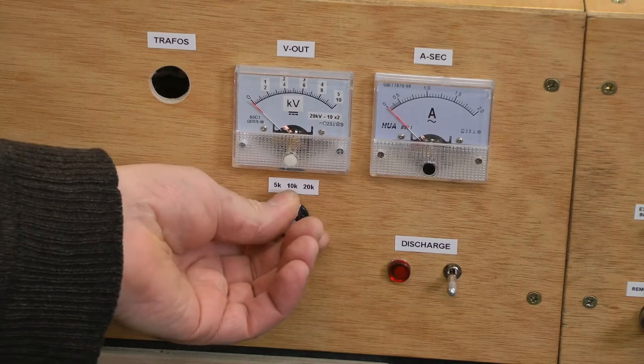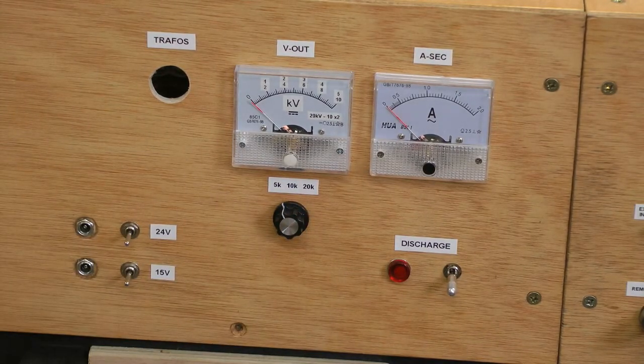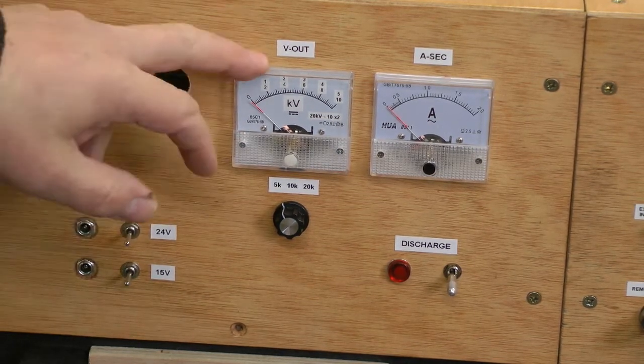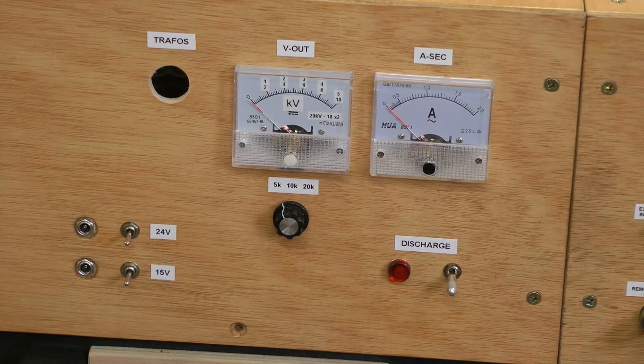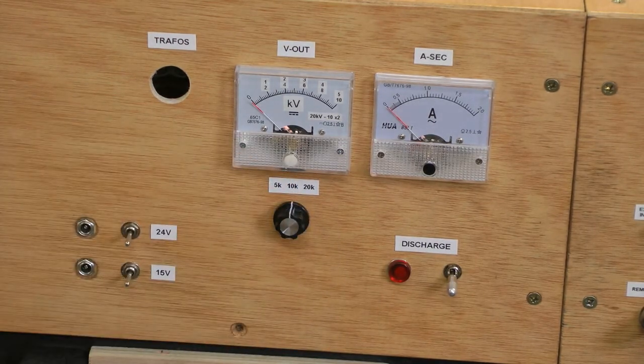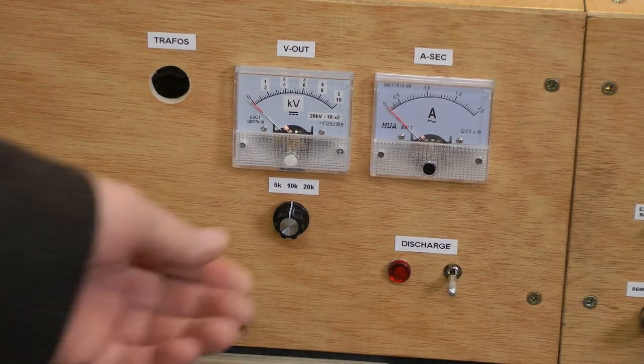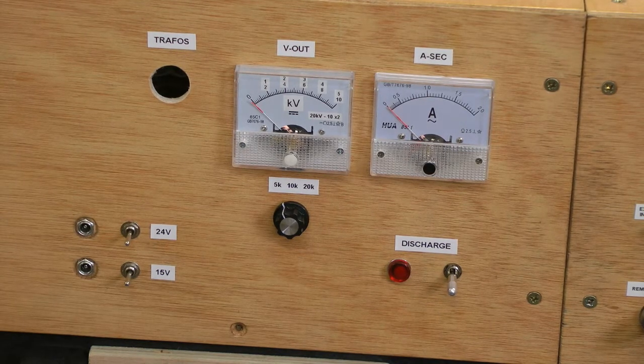You can also select the range, and these ranges are selected by using vacuum relays inside. This comes through a rectifier. So even if you're just using the raw output with no bridge rectifier or level shifter, this will give you essentially the rectified output. There's a half-wave rectifier with some high voltage smoothing capacitors, and then onto the divider chain, the resistor chain, which is selected by high voltage vacuum relays to give you the range. 20 kilovolts full scale is basically all the relays off. 10 kilovolts switches in 10 of those 20 resistors, and 5 switches in 5 of those 20 resistors.